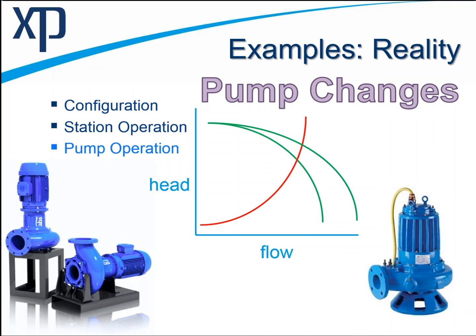And the opposite can be true also, where perhaps you get it perfect for two pumps running, and then when you change that to one pump, the configuration of the wet well and the pump itself operate really horribly. The way they operate doesn't work well at all. One thing we haven't covered, we'll cover it in a few slides, is the efficiency of these pumps, really important. But just know that it's more dynamic than you may at first think.